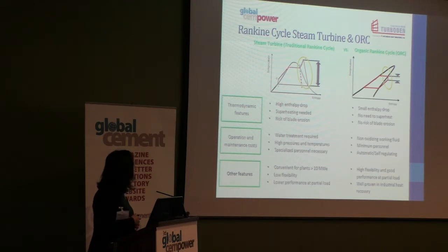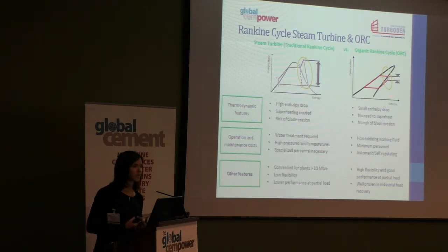In a steam turbine, when you have saturated steam, you must superheat it, otherwise you have liquid formation inside the turbine. With organic fluid, there is no need to superheat because due to the shape of the curve, when you enter the turbine, at the outlet you are always in a dry expansion. So you have a dry expansion with the organic fluid.